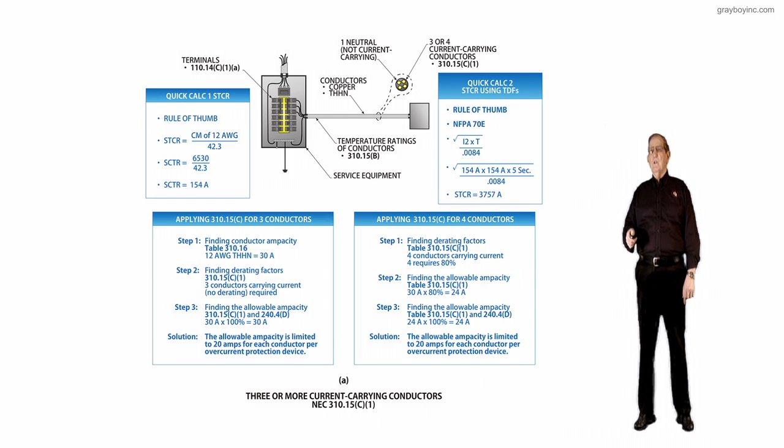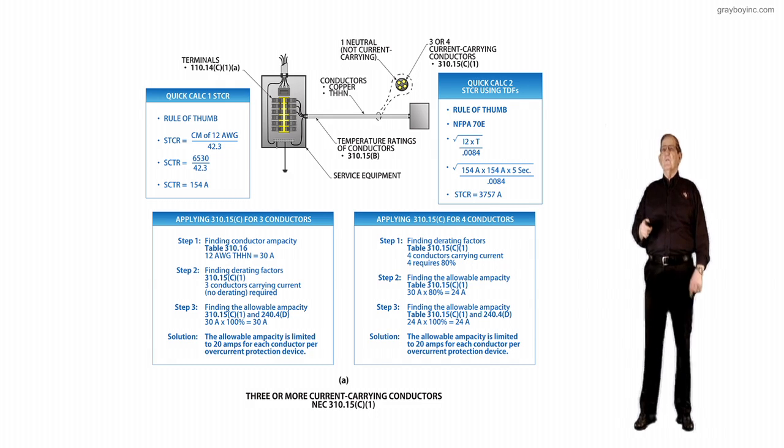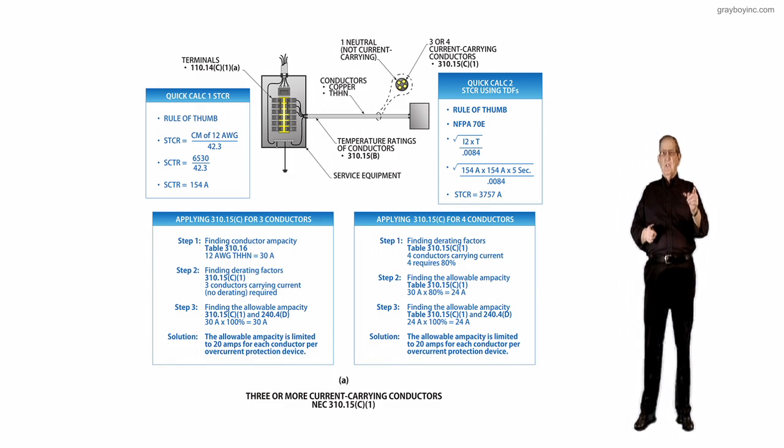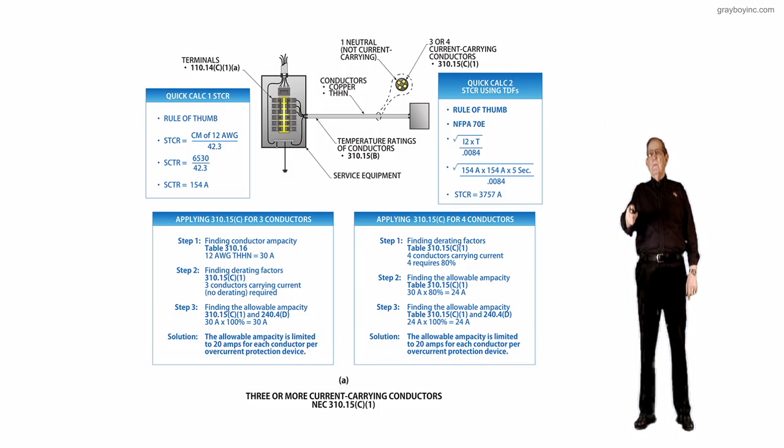So you could use a number 12 wire, 20-amp overcurrent device, and you're still in business there, even though you have 4 current carrying conductors. That's what these two calculations are designed to point out to you. That you can use the 90-degree ampacity to de-rate back to a 60, and that's what we've done right here in method 2. Keep that in mind that you cannot use the 90-degree ampacity except to de-rate back to a usable 60 or 75 based upon how the equipment is marked.